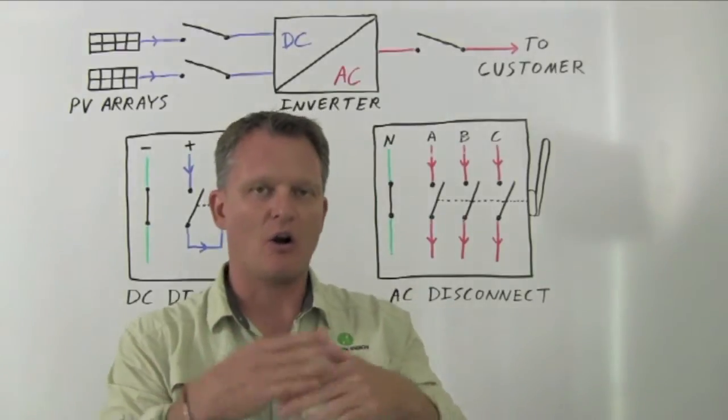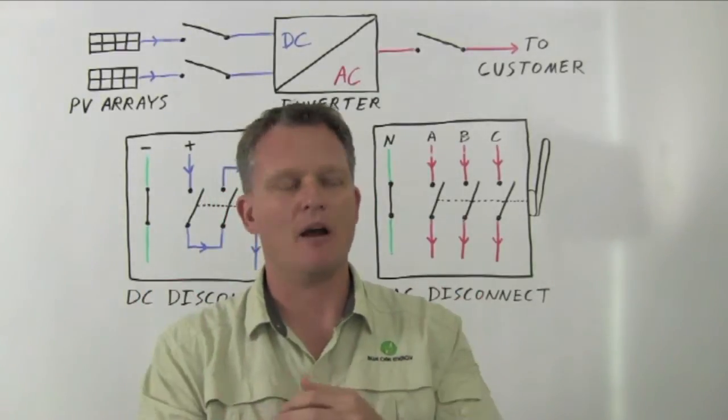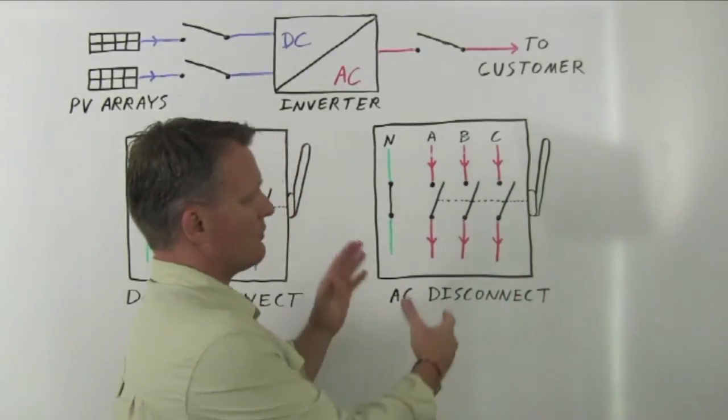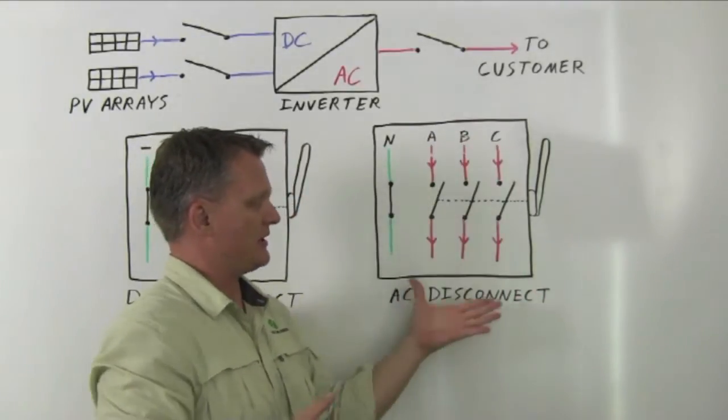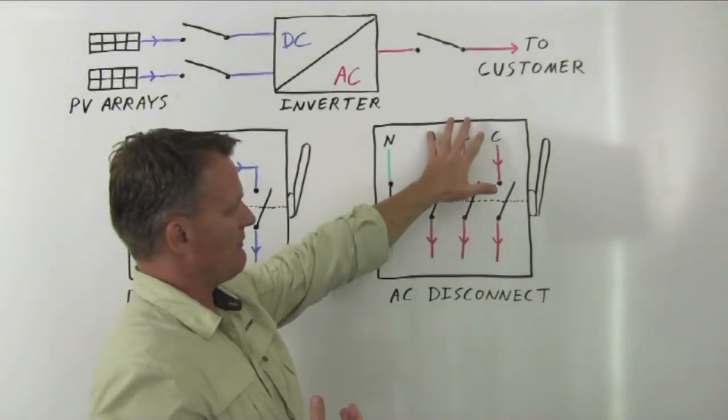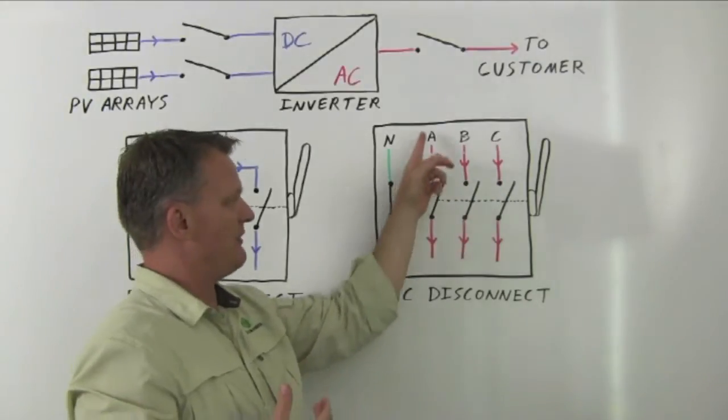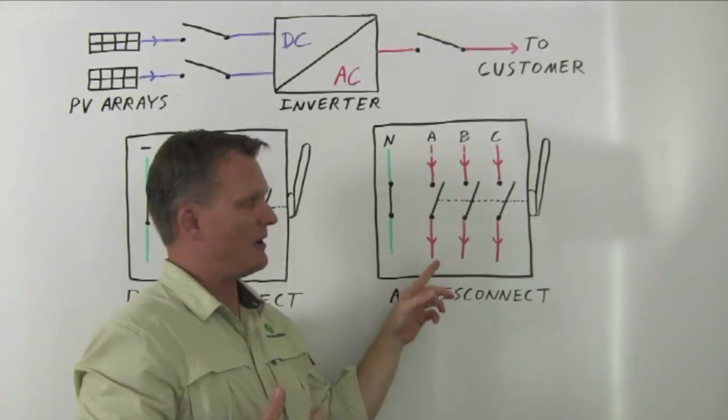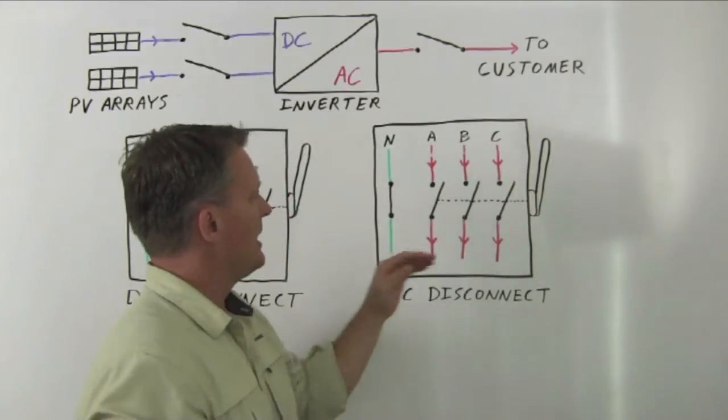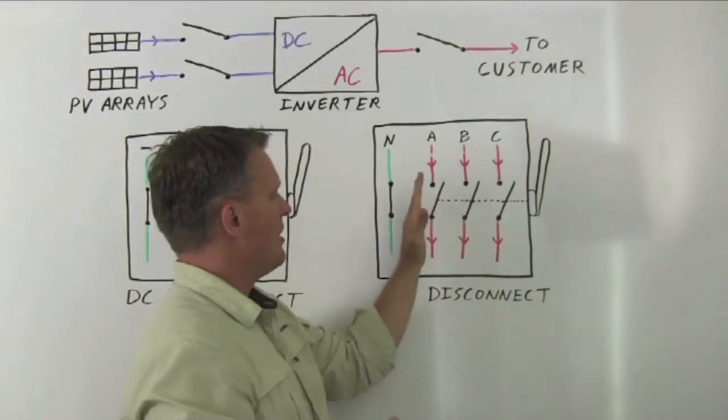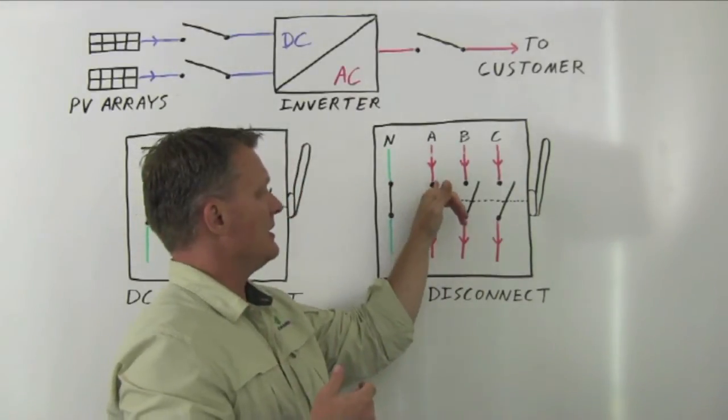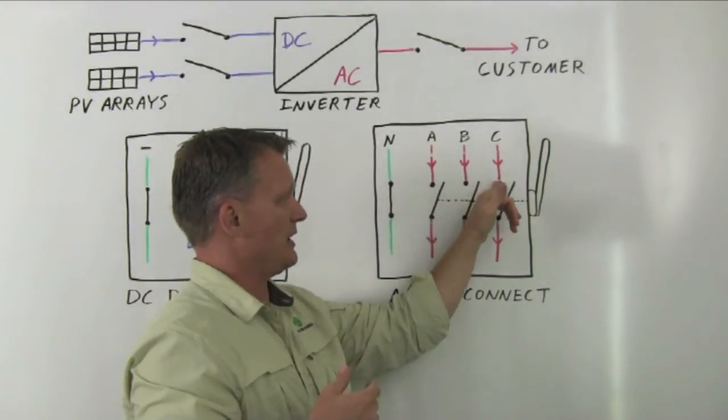Now, most commercially available disconnect switches are designed for AC current. And here's a typical wiring schematic of an AC disconnect where you've got your three phases coming in here. Each phase has a switch—you have A, B, and C, plus a neutral which is typically not switched. When you pull the handle on this disconnect, all three of these switches open up.